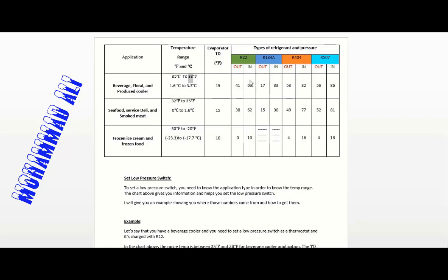You might ask why we applied the formula for the cut-out but not for the cut-in. Simply put, when the system is off, we don't need to apply that formula with saturation temperature. When the system is off, the box temperature and the evaporator temperature are equal, so we can directly convert the box temperature to pressure.